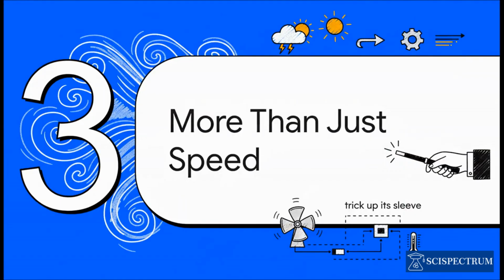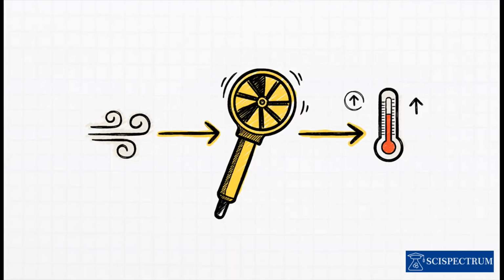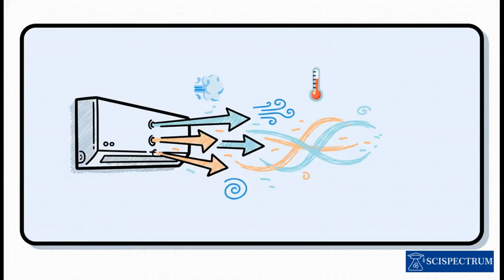But measuring wind speed is only half the story with this device, it's got another trick up its sleeve. Yep, it's also a thermometer. The probe has a clever sensor built in that can measure the temperature of the air flowing through it, in both Celsius and Fahrenheit. Why measure both at the same time? Well, wind speed tells you how much air is moving, but temperature tells you the condition of that air. If you're checking a heating or air conditioning system, you need to know both: is enough air coming out of the vent, and is that air hot or cold enough? This one tool answers both of those critical questions at the same time.